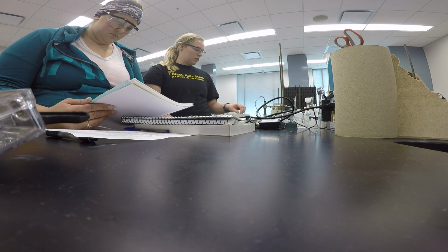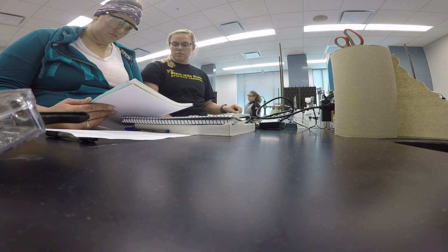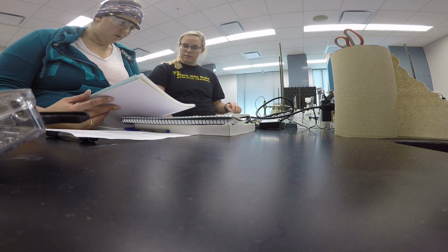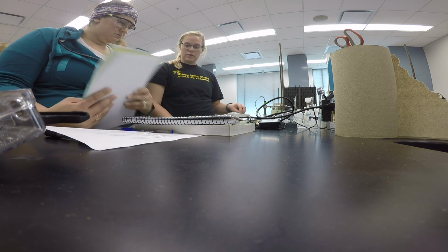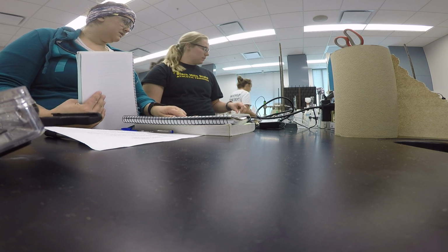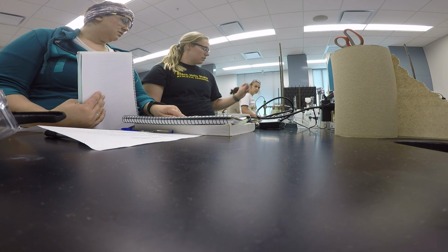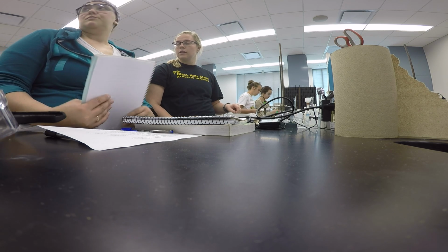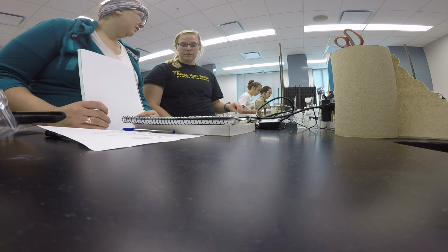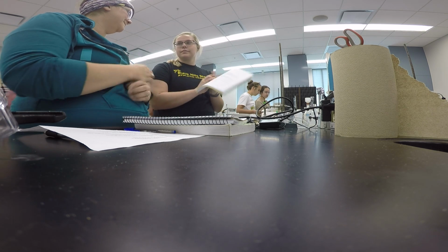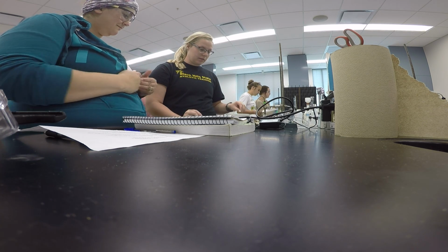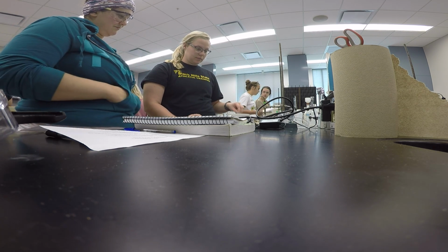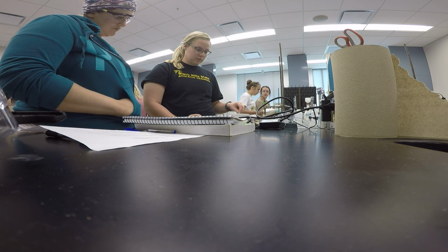Below our target pH, so we're going to have to recalibrate it multiple times. Because our target pH is 6 on one of them. 6 and 10. Yeah. We're going to have to go between 4 and 7 for one and 7 and 10 for the other. Yeah. So we have that, okay.